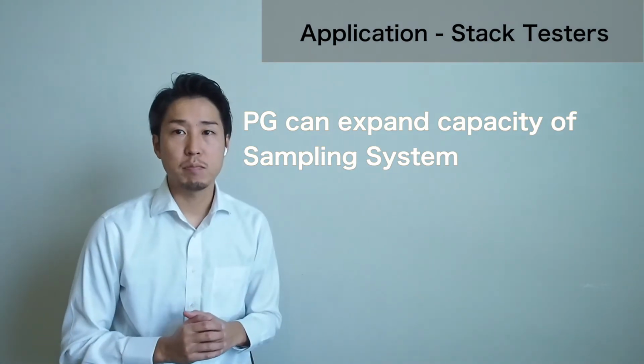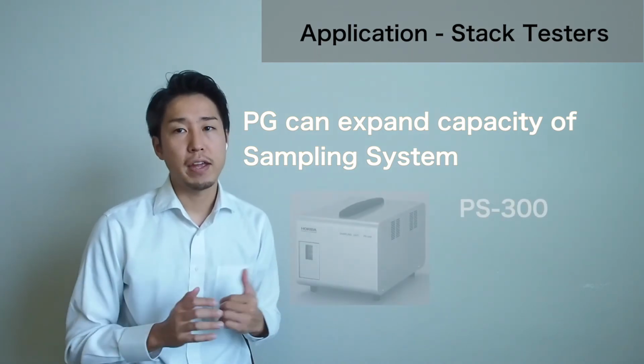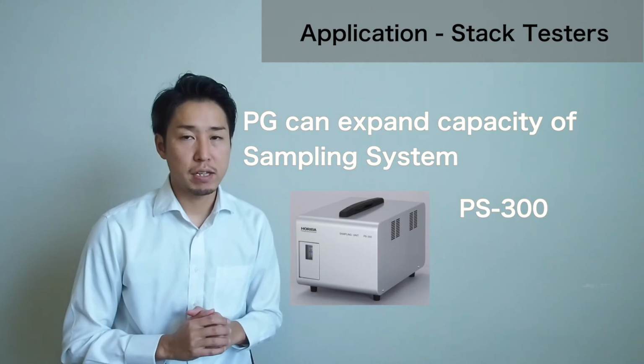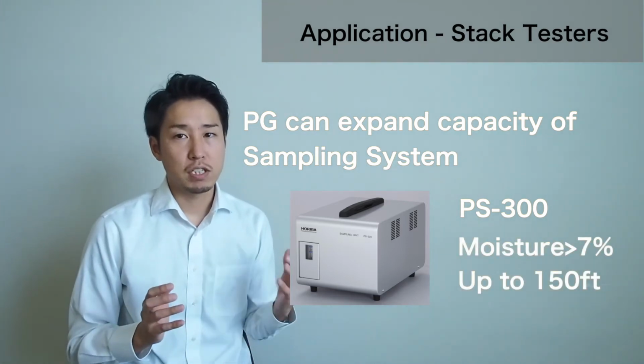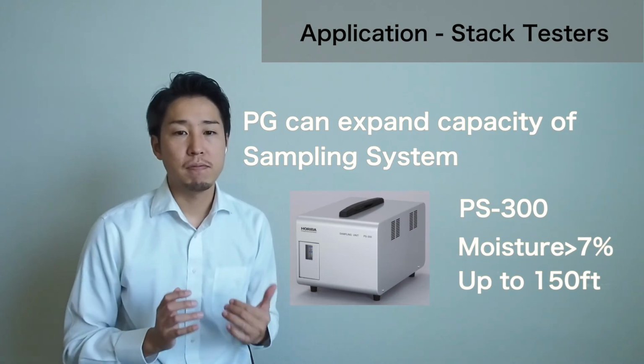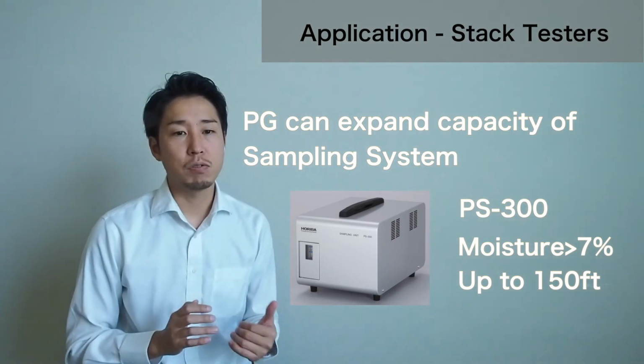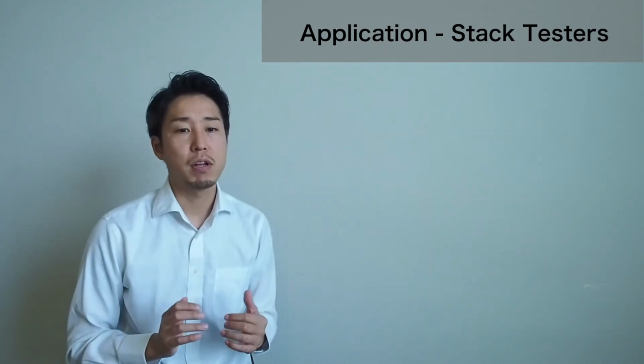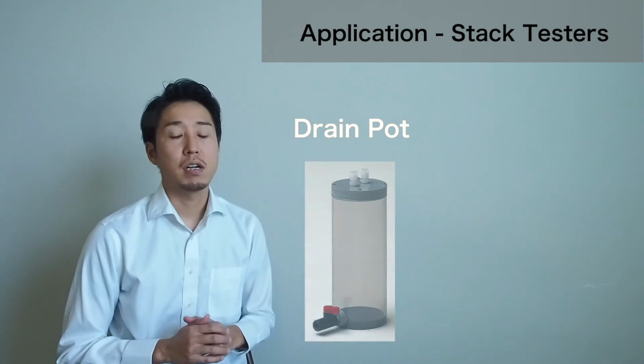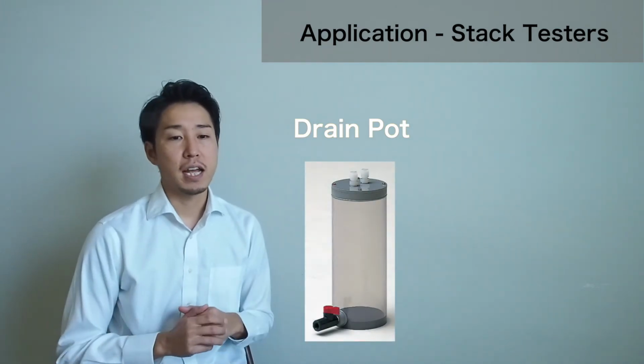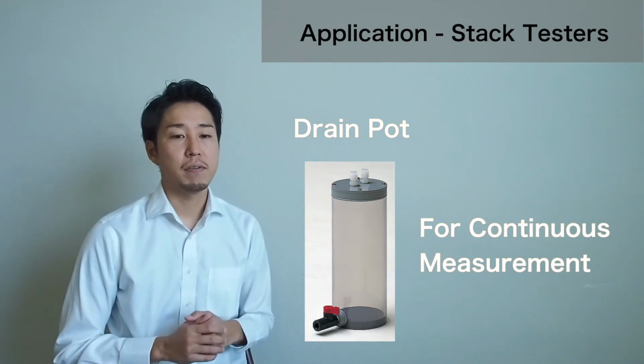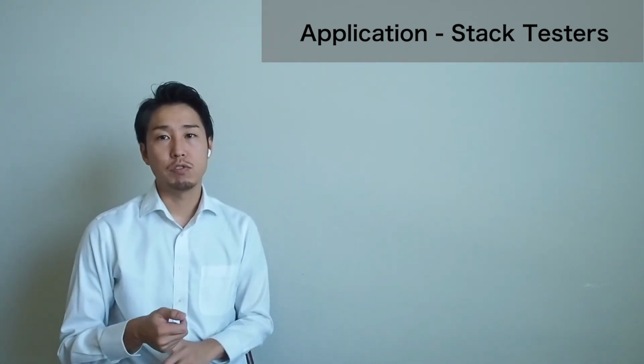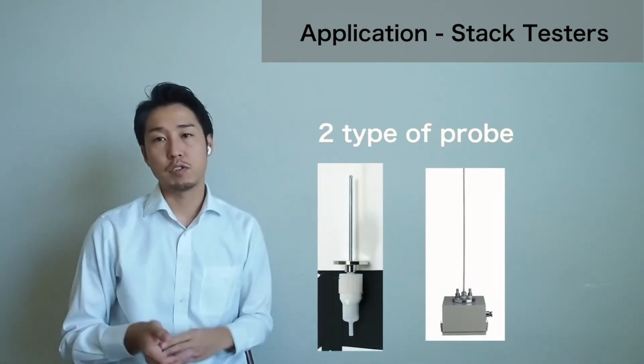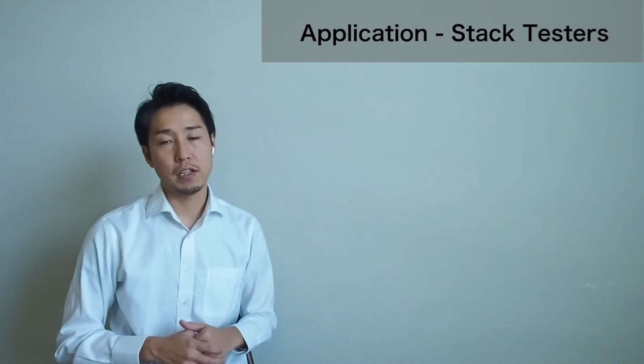If the sample gas contains more than 7% moisture, please think about using the PS300. This is an external cooler, and also this PS300 contains a much more powerful pump built in, so you can pull the sample up to 150 foot. A drain pot will help to drop the moisture, especially if you need to measure the gas continuously. It would be better to have a drain pot. This will help to keep the sampling cooler healthy. HORIBA can provide heated bundle tubing, probe, temperature controller, stuff like that. So let us know how we can help to provide the quote.